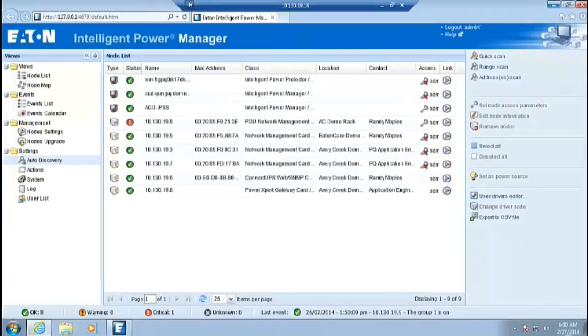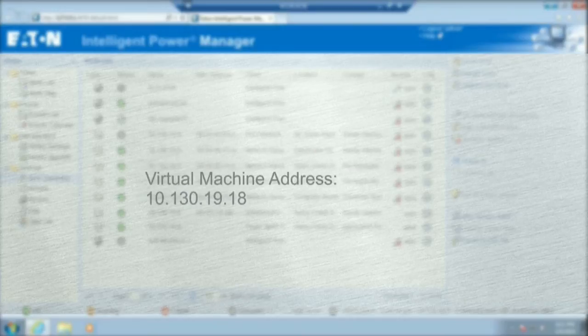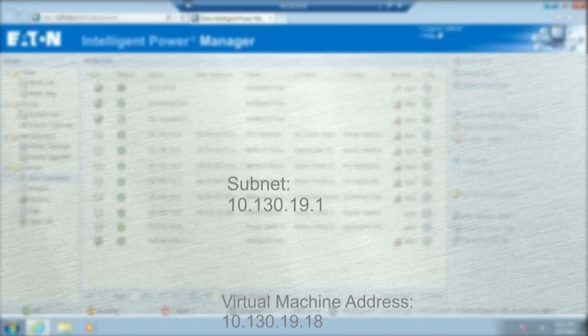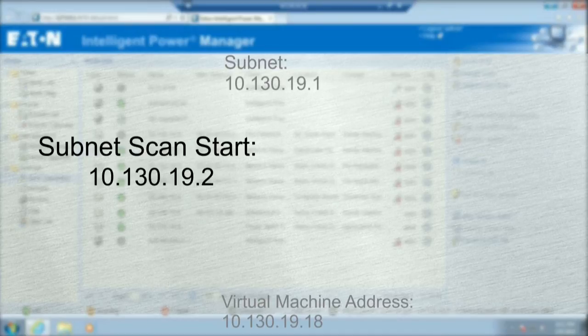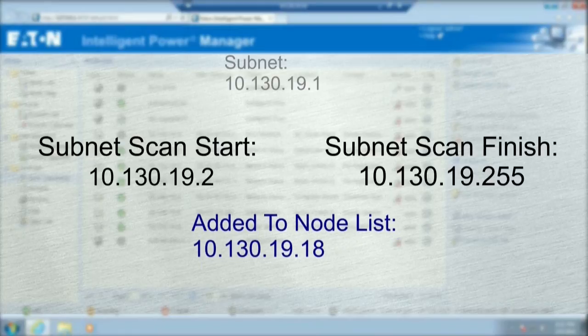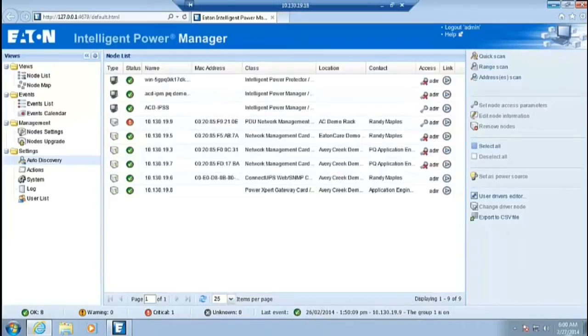For example, our virtual machine address is 10.130.19.18, with the subnet being 10.130.19.1. The Quick Scan tool will search in the parameters of 10.130.19.2 through 10.130.19.255. If the node's IP address is within the subnet parameters, it will be added to the node list. If the node's IP address is not within the parameters, it will be skipped. Quick Scan will initiate each time IPM is opened. Once complete, all of the nodes detected will be shown in the node list.